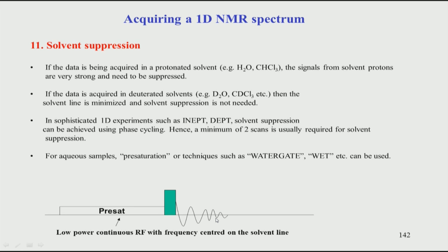and the solvent peak oscillation is gone. So, when you do a Fourier transform and finally get a spectrum, your spectrum will not contain any solvent peak. This is one way to do the solvent suppression, but it is a very crude approach, a brute force approach. The reason being, you are simply applying a weak radiation at the solvent line. So, this is not really the best solution many times, and therefore pre-saturation, although it is the most common approach, is not the best approach.